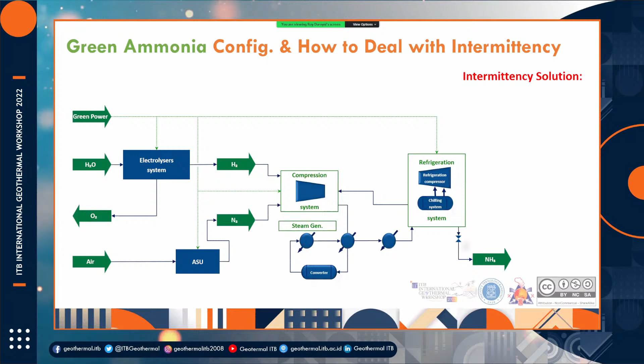First, as I mentioned, we need a bigger power source, bigger capacity. Then we need to add battery. Then we need hydrogen storage, maybe a small one, because hydrogen must keep being supplied to the ammonia plant since it cannot be shut down. And as mentioned, we also need to turn down the ammonia synthesis loop to very low capacity, which is also a challenge since the plant cannot be shut down.